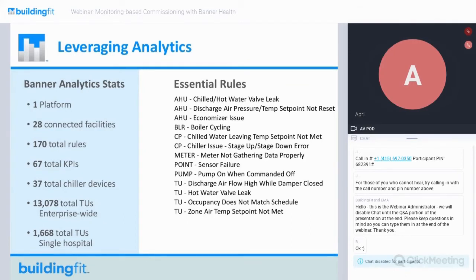I selected a sample of rules that would likely be useful across a majority of buildings and systems. Of course, depending on the systems you have, your essential rule list may be a little different from this one. So you can see the first three on my rule list are targeting air handling units. These are rules designed to detect chilled water and hot water valve leaking, discharge air temperature set point resets, so optimization resets. Also targeting making sure your economizer is functioning properly.